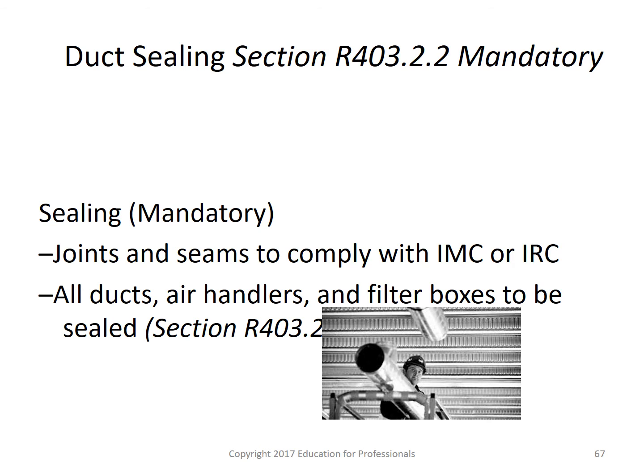And with all of this on air infiltration, we'll take a look at duct sealing. Found in the duct sealing section, R403.2.2, and of course sealing is mandatory. The reason for this is to keep the interior conditioned air separate from any air that would be found in the plenums or chases or other air spaces that the ductwork moves through.